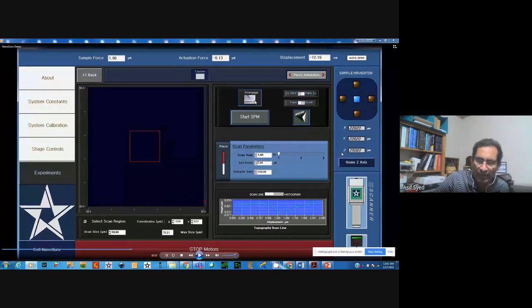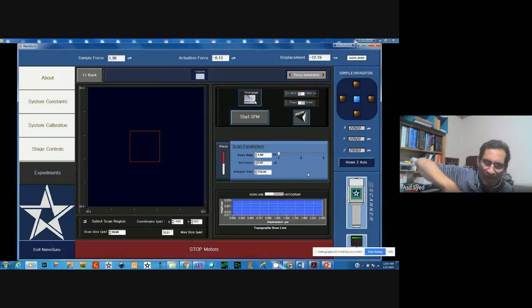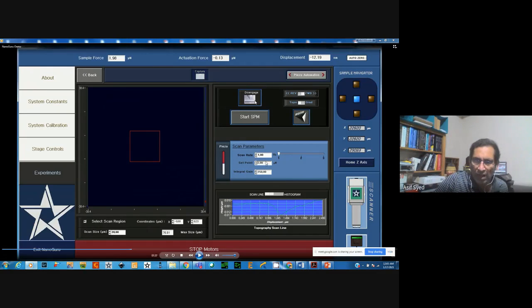So what it means is that it scans one time, goes full and then comes back. Now, with 1 hertz, we can select the force you want to maintain between the tip and the sample during scanning, which is about 2 micronewton. You put that over here as the set point, and then this is a feedback loop. Basically, we are scanning with the tip left and right, and while scanning we are trying to maintain this force, which is called the set point.